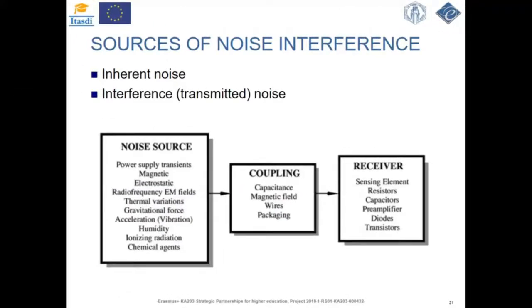Any sensor, no matter how well it's designed, never produces an electric signal that is an ideal representation of the input physical quantity being measured. One of the causes for that is noise interference effects. Noise in the sensors and circuits may be a substantial source of errors, so we have to consider it very seriously. On this slide, we show two types of noise: inherent noise and interference, or transmitted noise.